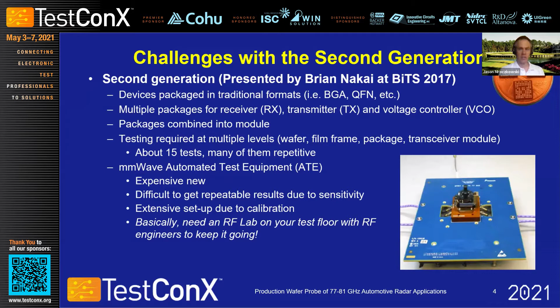This, as I mentioned, was very new and expensive technology to be able to run at 80 gigahertz, take that signal all the way from the device itself out to the tester. Cabling itself was very expensive. Repeatability was an issue because anytime you touched any of the componentry, recalibration was required. The easiest way to calibrate seemed to be golden devices, but those devices would come out of calibration and need to be reset. So, there were a lot of challenges. As I mentioned, you essentially had to bring the lab bench to the test floor, along with expensive RF engineers to keep it going. So on comes the third and current generation of devices.